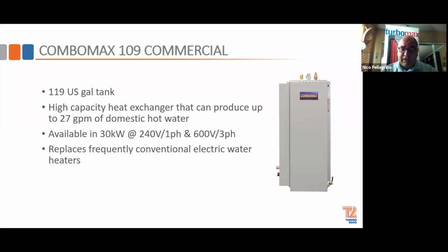Works very good in schools when schools are shut down. In the summertime, they don't have to run big boiler plants. Their cleaning staff can use these tanks in lieu of the big boiler plants and still have lots of hot water. Gyms like it because, again, the footprint is small. They don't have to have big storage tanks, and we keep up to the demand that they have in gymnasiums and spas.